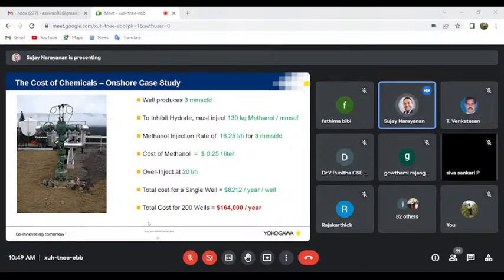Just to give you an example, a well produces 3 million standard cubic feet per day of natural gas. Now, to stop the hydrate formation, we must inject a chemical called methanol at 130 kilograms per million scf, million standard cubic feet. If you calculate it for 3 MMSCFD in terms of volumetric flow, it is 16.25 liters an hour, 130 kilograms of methanol. Now 1 liter of methanol costs 25 cents, a quarter of a dollar.